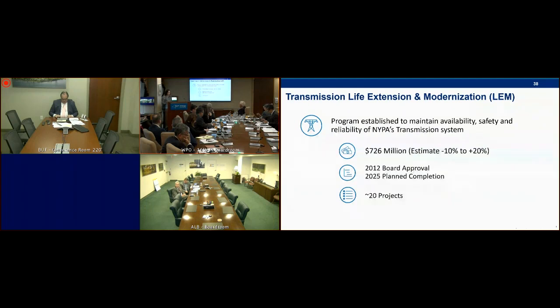In 2012, board approval was received to embark on the TLEM program, established to maintain availability, safety, and reliability of NYPA's transmission system, which comprises a significant portion of the transmission backbone in New York State. At the time, a majority of the equipment had exceeded its service life, and several significant failures were experienced, including an oil-filled circuit breaker at St. Lawrence and two auto transformers at Massena substation.